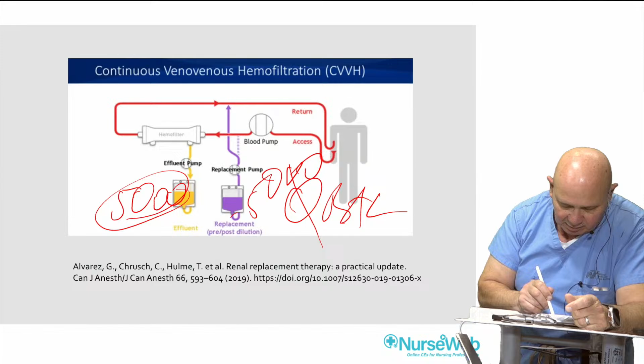But here you see you're removing the effluent, but your replacement is post-filter. So whatever you remove here, and remember, this is going to be zero balance. If I remove 5 liters here over whatever period of time, 5 liters here has to go back into the blood. And that's done automatically by the machine. The machine cannot add volume to the patient.